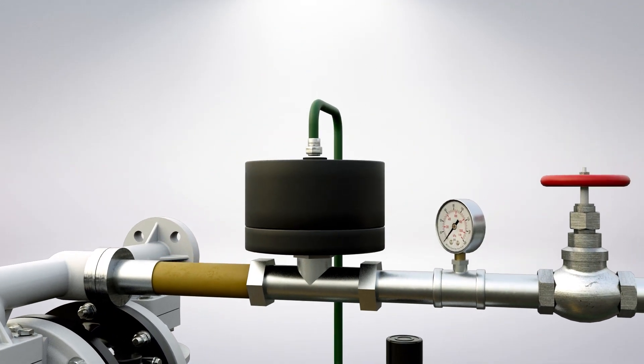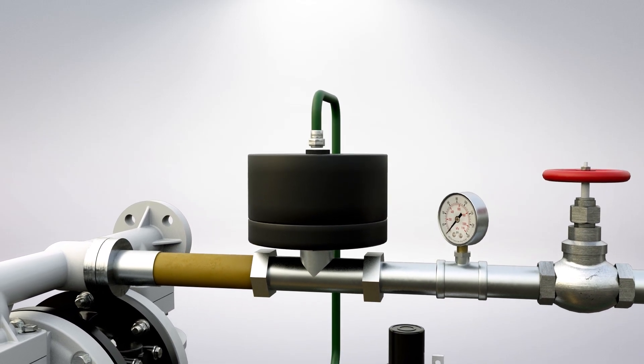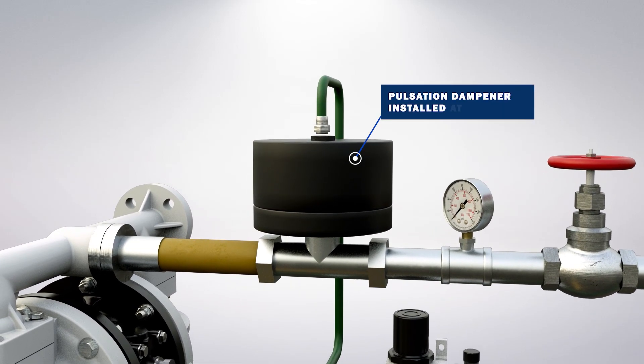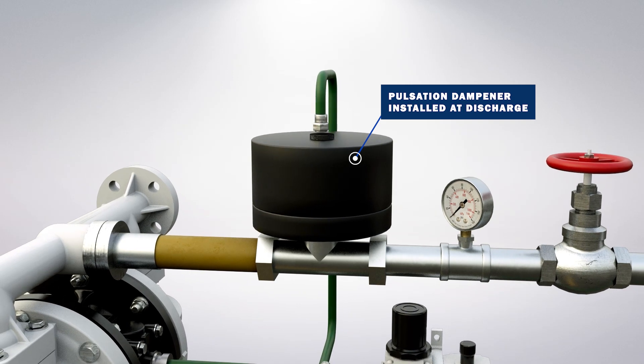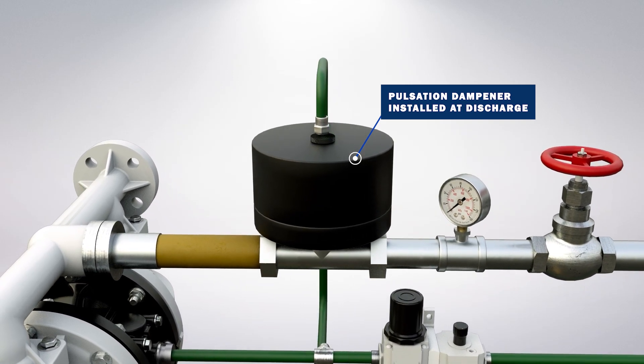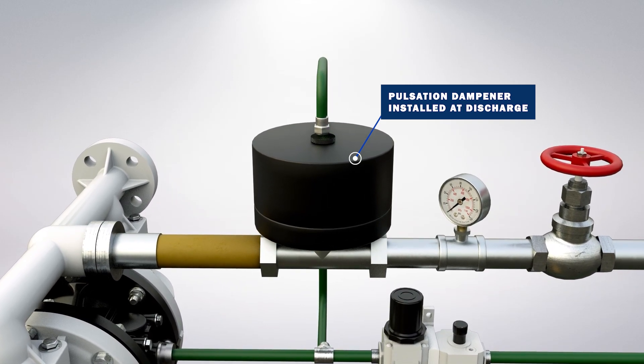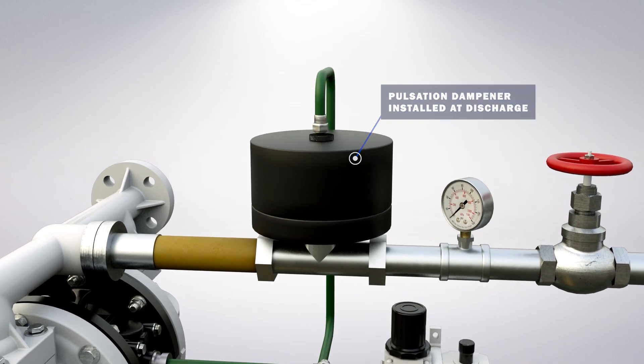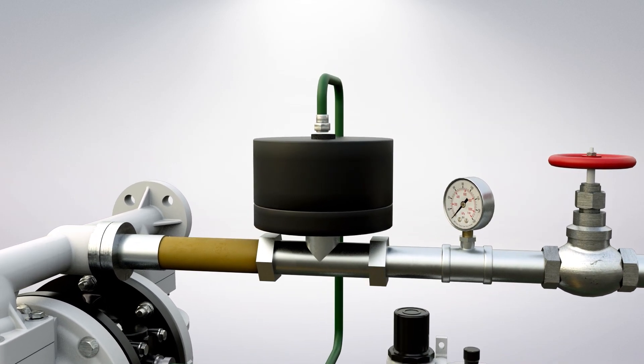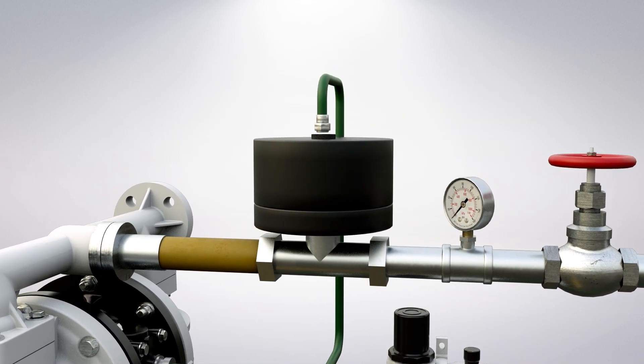For applications where the effects of pulsation should be reduced, a pulsation dampener can be installed on the discharge side of the pump to help provide a smoother discharge flow. This function is critical in applications that need to minimize system vibration to protect and enhance the accuracy of downstream instrumentation. It also extends equipment life by reducing the load on the pump.